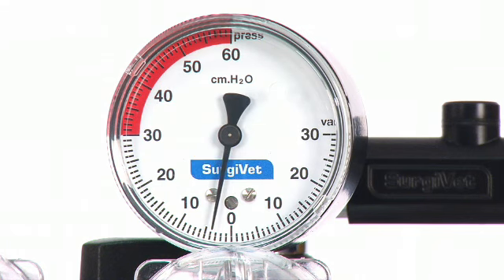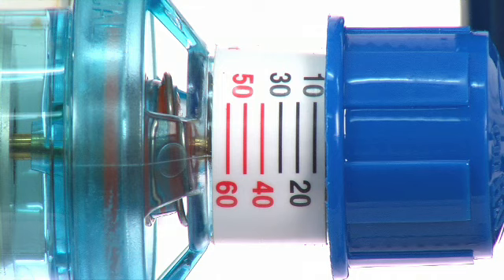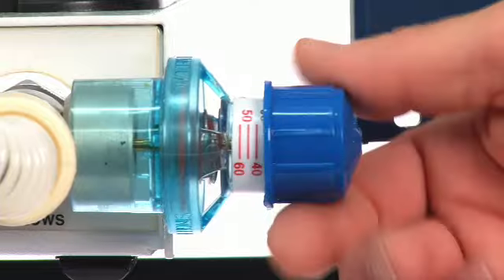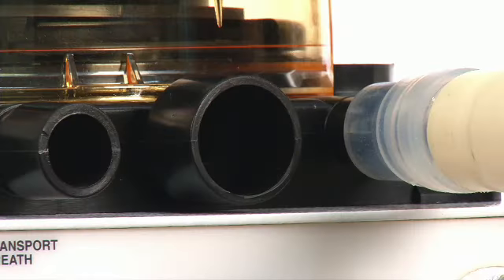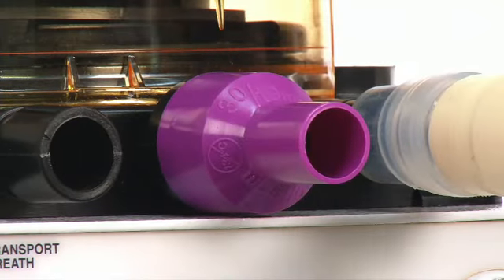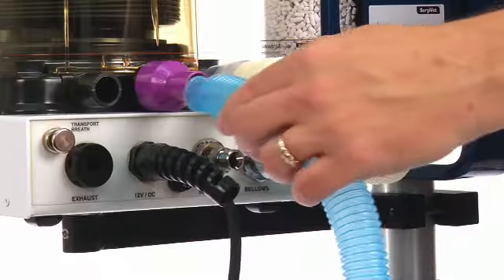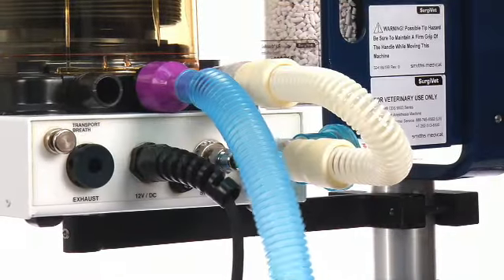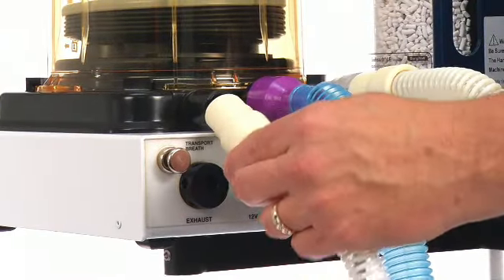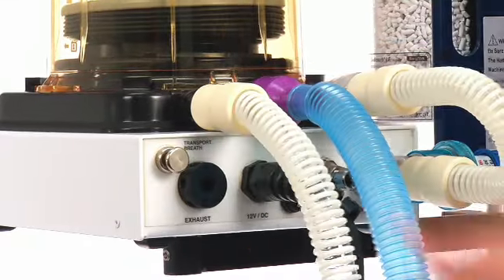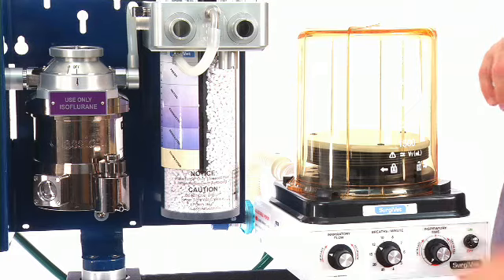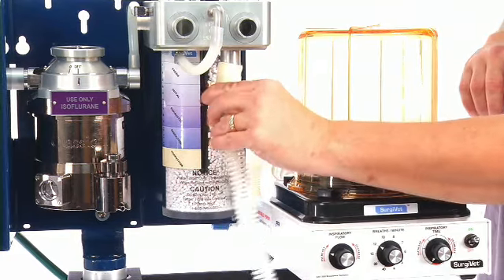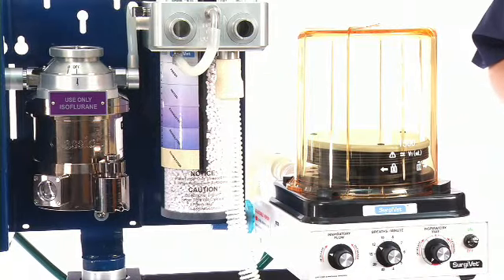It can be set to a desired pressure of approximately 10 centimeters H2O when fully open and 60 centimeters H2O when closed. The gas evacuation port is where the expired gases are scavenged from the circuit. To connect the scavenged tubing to this port, the purple 30 mm by 19 mm adapter is necessary. The supply hose inlet is where one end of the 48-inch cuffed hose is connected. The other end of this hose connects to the bag port on the anesthesia machine.